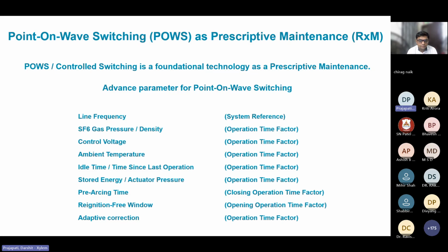The control voltage itself also influences the operating time. Ambient temperature, the idle time, the time since the last operation was done, stored energy, or if it is an air blast circuit breaker, the actuator's air pressure, and the pre-arcing time, which influences the closing operation.